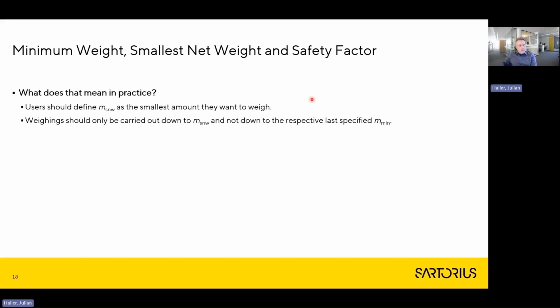So how does that work in practice, or what does it mean in practice? Users should define a smallest net weight for the balance as the smallest amount they want to weigh on it. Weighing should then only be carried out down to this value and not down to the respective last defined minimum weight. I will explain that with an example of some simulated minimum weight determinations over time. The minimum weight changes from time to time, each time it is determined, due to changed environmental conditions, random variations, or also a change of the balance.